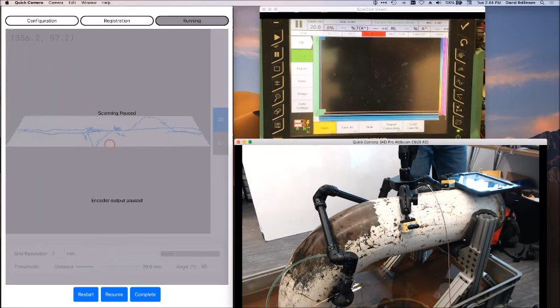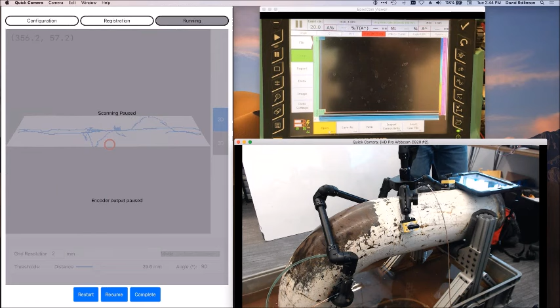Yes, so this is a dual element transducer. What I was doing before was phased array. My understanding is that there's ways of splitting out that phased array to multiple transducers. In short, if you can mount it and the flaw detector can handle it, we can handle that. What I'm going to show in the integrated solution later on, what we're providing is going to be single channel, could be dual element, like pitch catch probes. But again, if the flaw detector supports it, we can work with you to mount them whatever way makes sense for that.